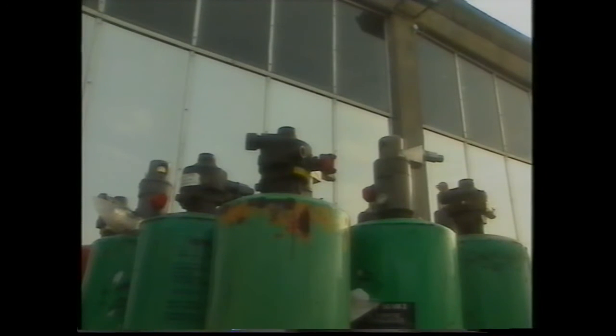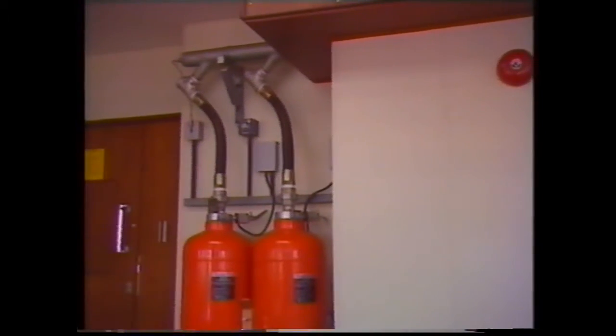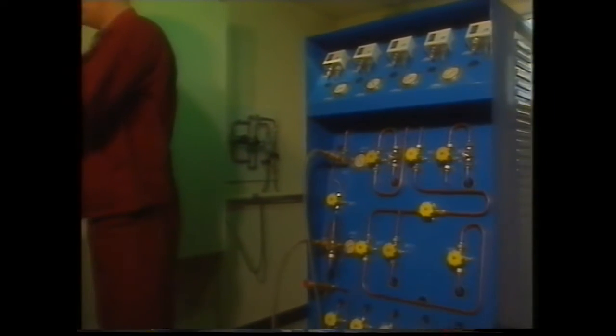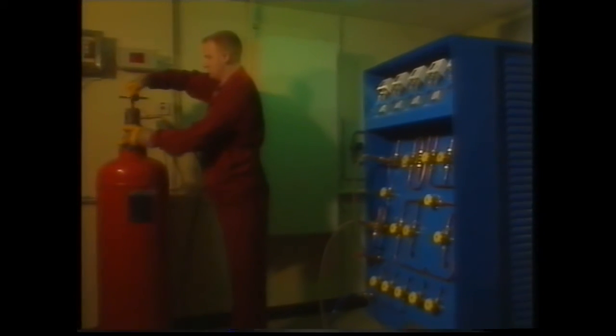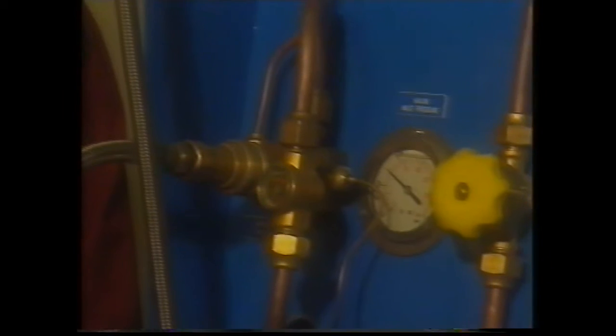Within the same environment, a separate service is offered for the recovery of Halon 1301 from cylinders in fixed systems. Centered around a second dedicated unit, the attention to quality throughout the process remains exactly the same. Here, single cylinders take the place of multiples of extinguishers. Both the Halon recovery units offer a speed of operation and level of efficiency that is very impressive. And fully loaded, up to 3 kilos of Halon 1301 or 1211 can be processed every minute.